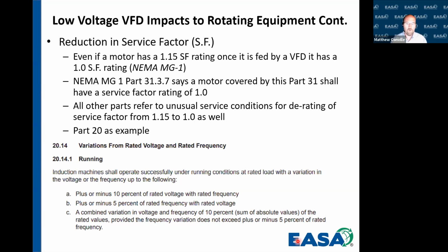So more or less, if we operate a variable frequency drive lower, on a 60 hertz machine, lower than 57 hertz, then we've automatically gotten rid of that service factor from a 1.15 to a 1.0 in any other condition, along with the fact that 31.3.7 says that anytime we're using a motor on a variable frequency drive, it has a service factor of 1.